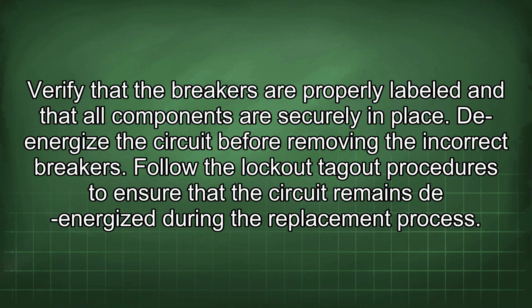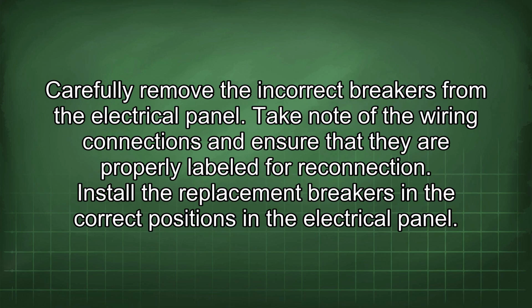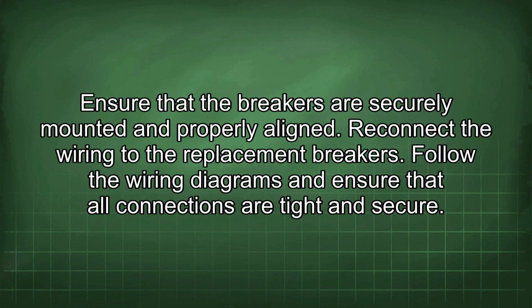during the replacement process. Carefully remove the incorrect breakers from the electrical panel. Take note of the wiring connections and ensure that they are properly labeled for reconnection. Install the replacement breakers in the correct positions in the electrical panel. Ensure that the breakers are securely mounted and properly aligned. Reconnect the wiring to the replacement breakers. Follow the wiring diagrams and ensure that all connections are tight and secure.